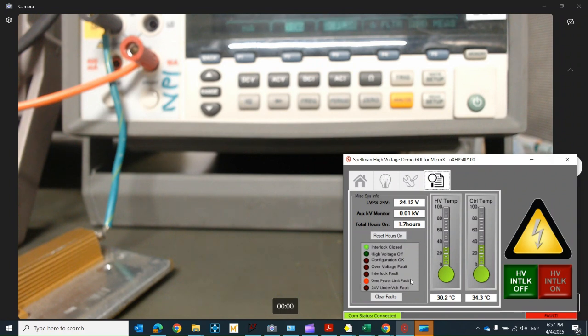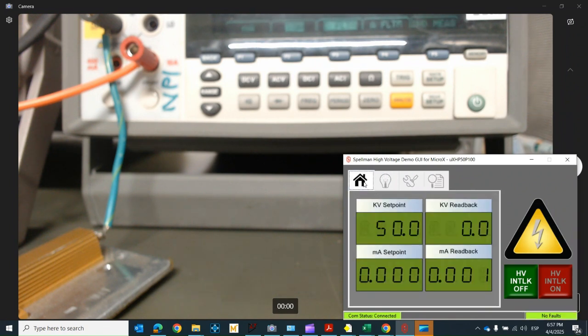Readback readings will exceed the 25 watt setting, issuing an over power limit fault. Check on datasheet. Remove JP2. Also return factory settings to the previous value.